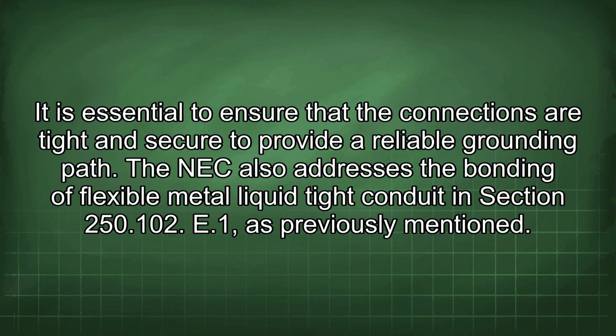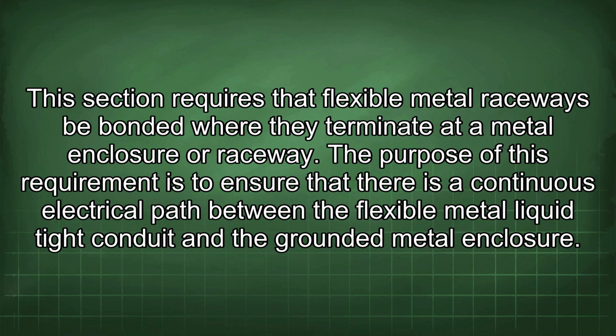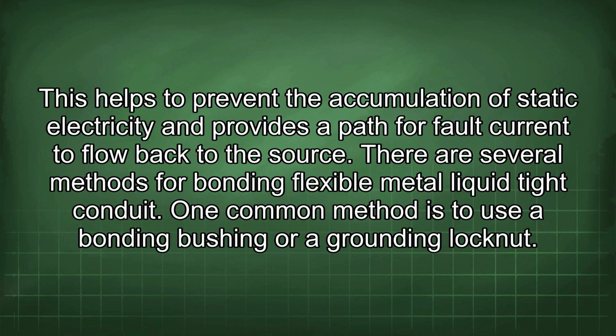The NEC also addresses the bonding of flexible metal liquid tight conduit in section 250.102(E)(1) as previously mentioned. This section requires that flexible metal raceways be bonded where they terminate at a metal enclosure or raceway. The purpose of this requirement is to ensure that there is a continuous electrical path between the flexible metal liquid tight conduit and the grounded metal enclosure. This helps to prevent the accumulation of static electricity and provides a path for fault current to flow back to the source. There are several methods for bonding flexible metal liquid tight conduit.